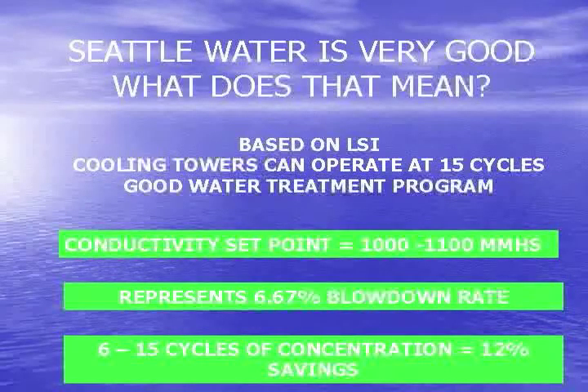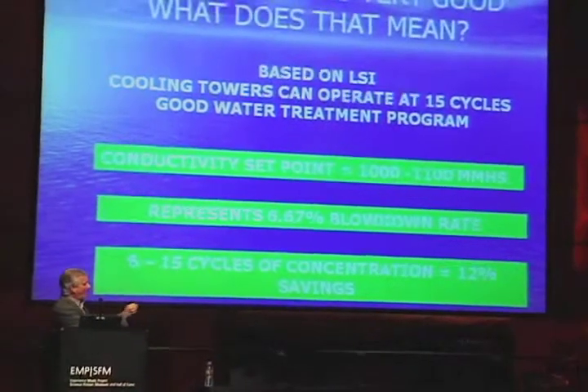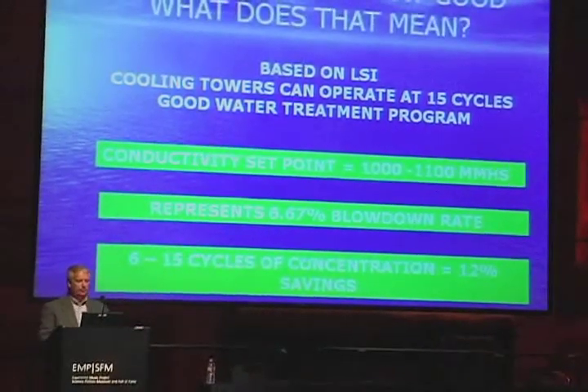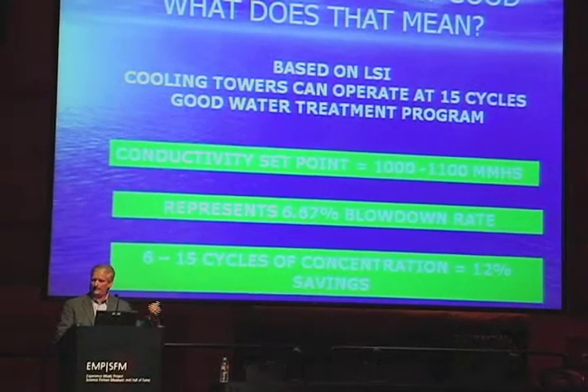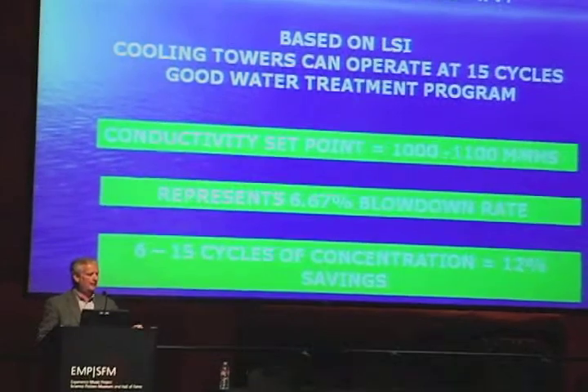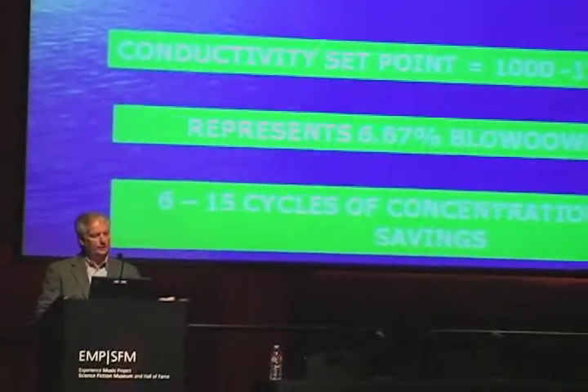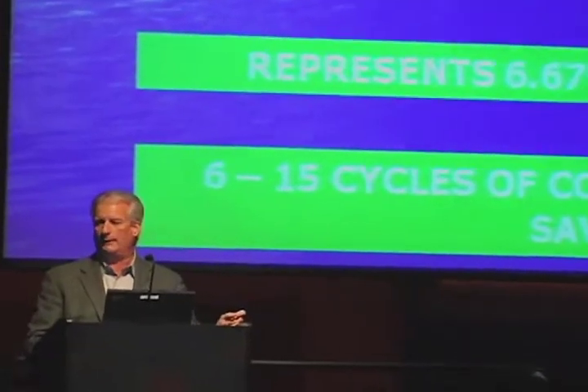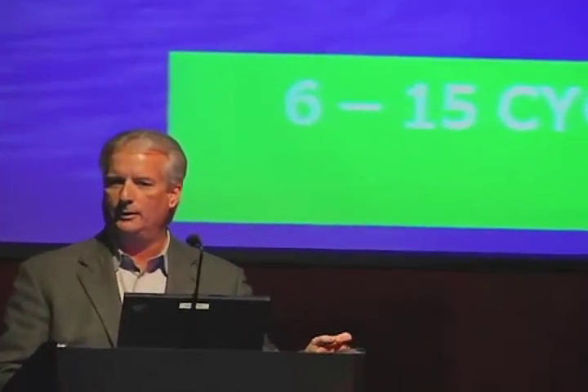So what I did is I plugged Seattle water into this model and did some calculations to find out where you should be. Based on the LSI, the cooling towers can operate at 15 cycles of concentration in Seattle. 15 cycles. You're way out here on that graph, which is very good. Now, you need a good water treatment program to prevent scaling, because as you push it out there, you are going to see some deposition if you don't have good water treatment. So your conductivity set points on all your controllers should be around 1,000 to 1,100, unless you have varying makeup source waters. One of your homework assignments is, when you go back to your cooling tower controller, see if it's between 1,000 and 1,100. If it's not, ask your water treatment supplier why it's not there.